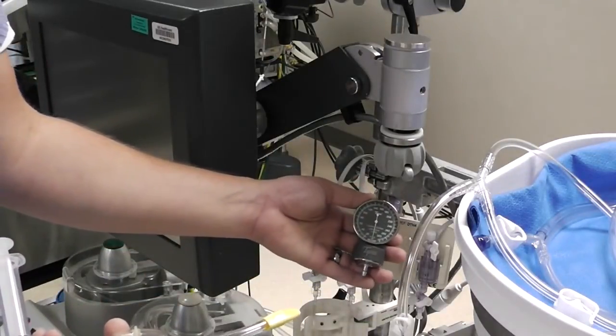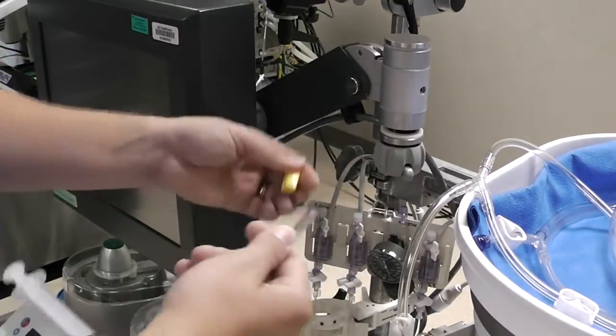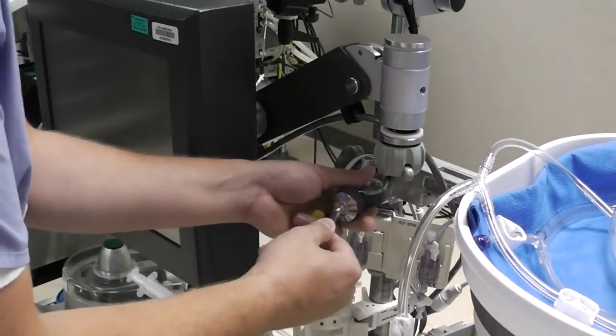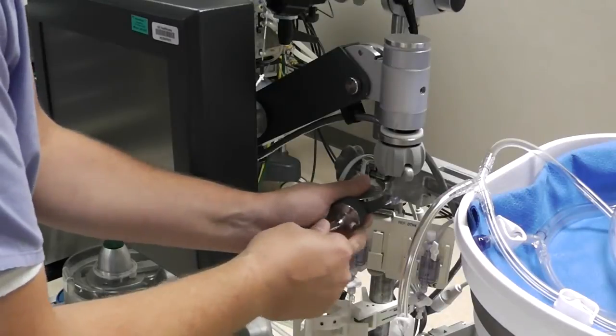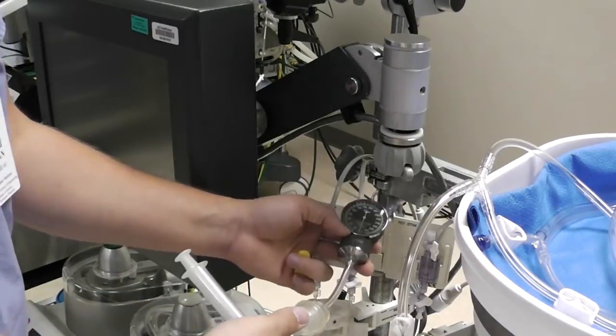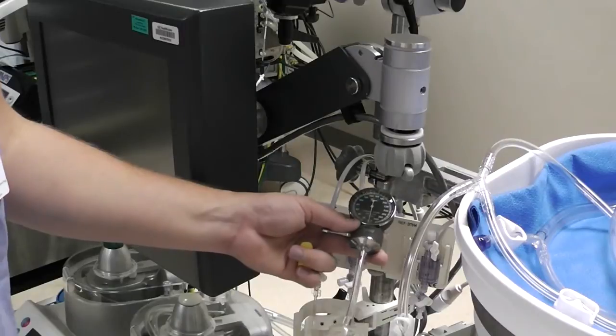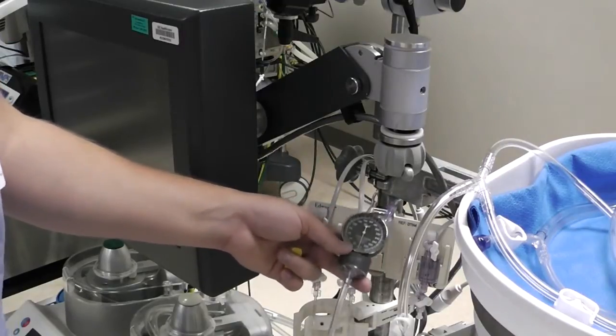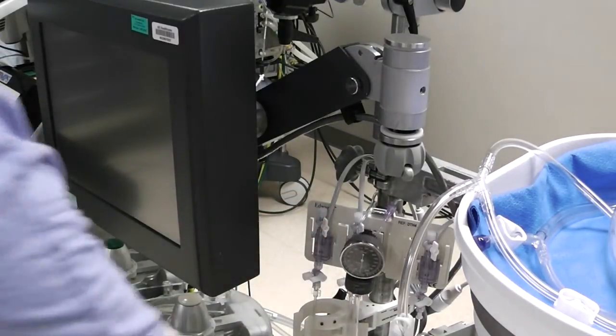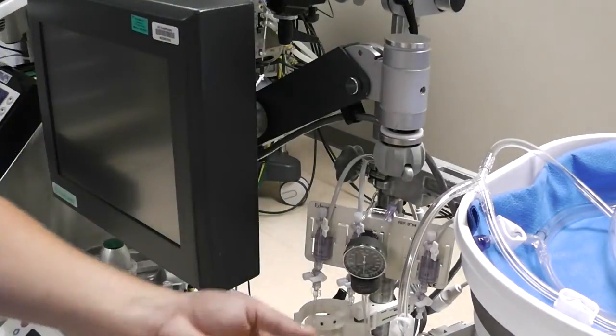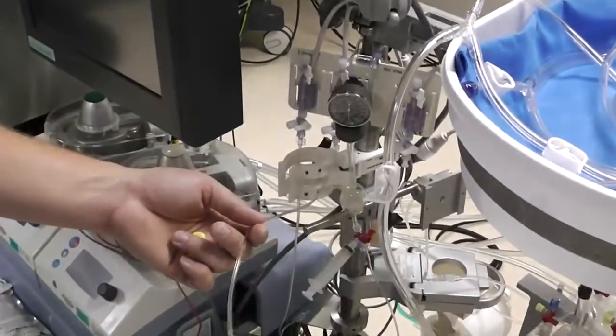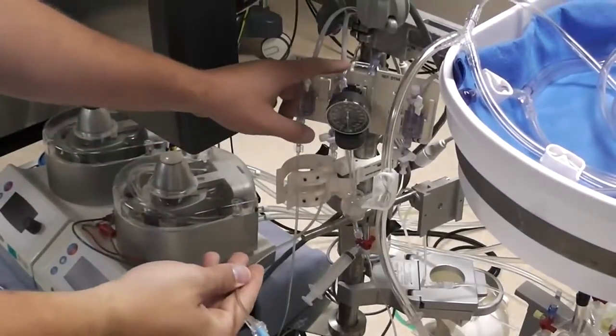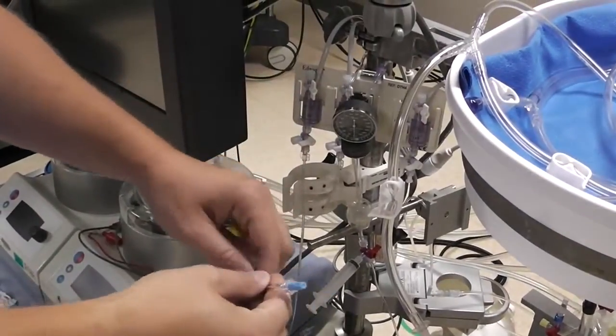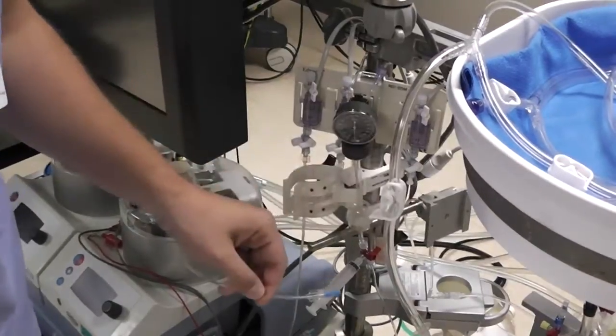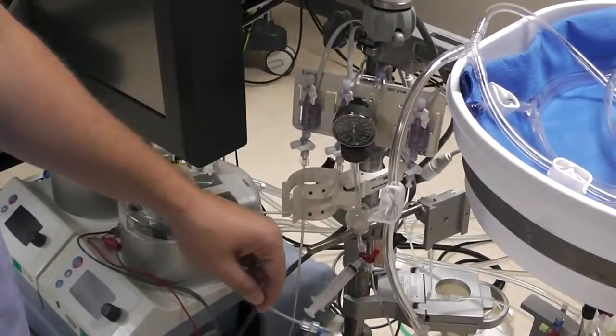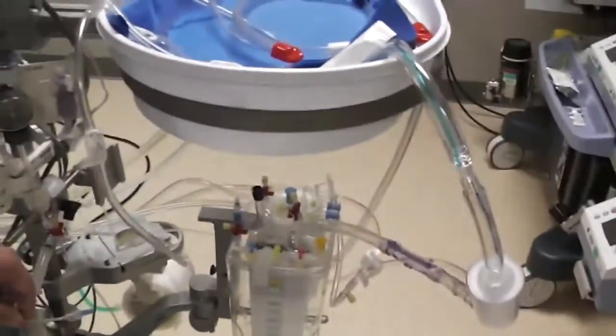Next we're going to attach the arterial pressure monitoring bulb, and this is going to go to the pressure gauge here. So we'll take the yellow cap off the end, and we're just going to loosely put that onto that connection. We're going to be removing that later during priming, so you don't want to shove that on there all the way. While we're over here, we're going to take the line off the venous pressure transducer and connect it to the stopcock on the cardiotomy where it goes. Let me get that.